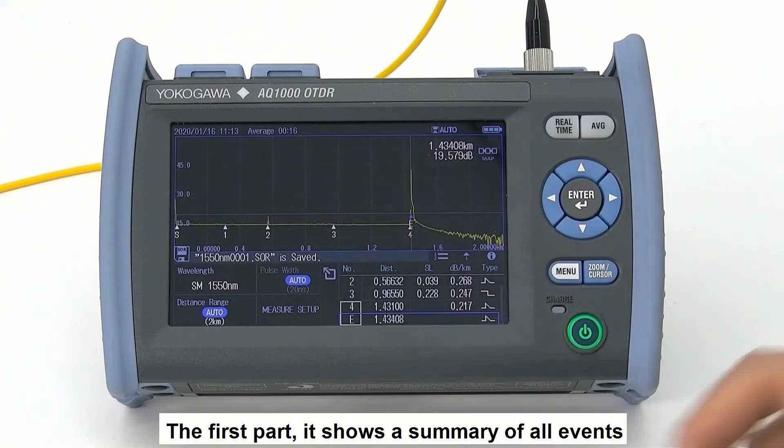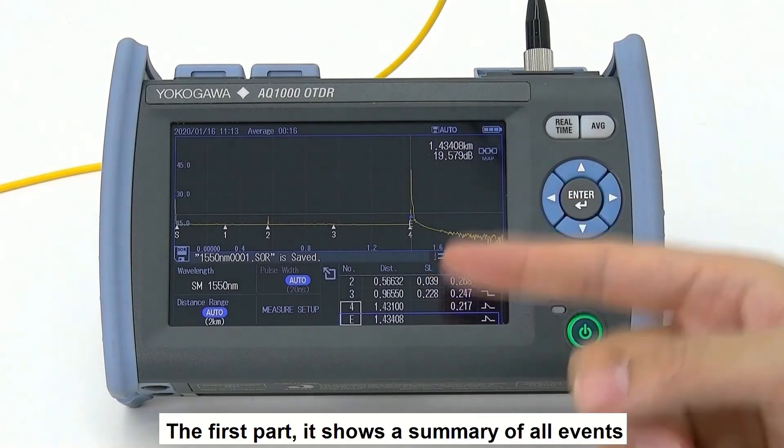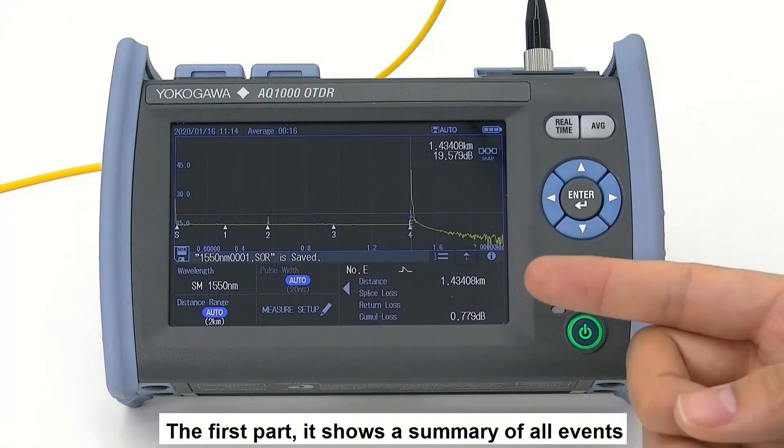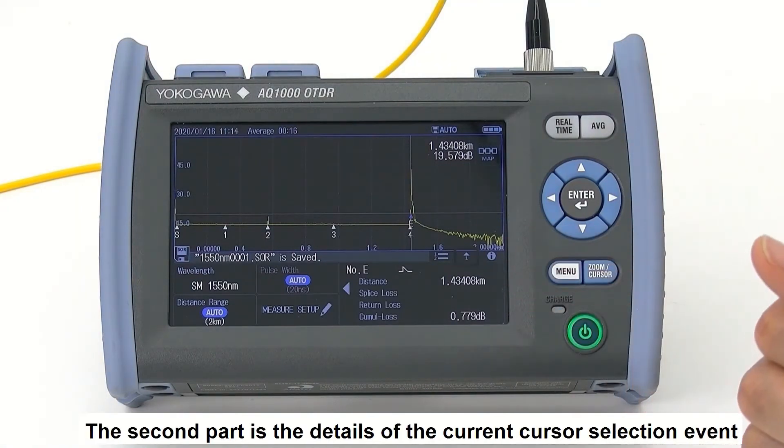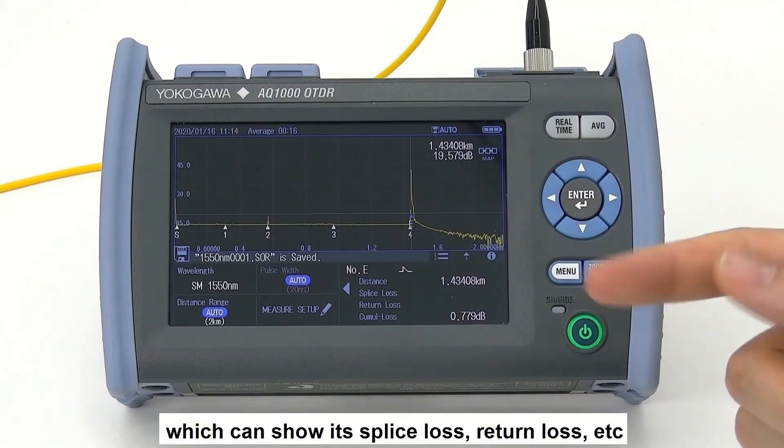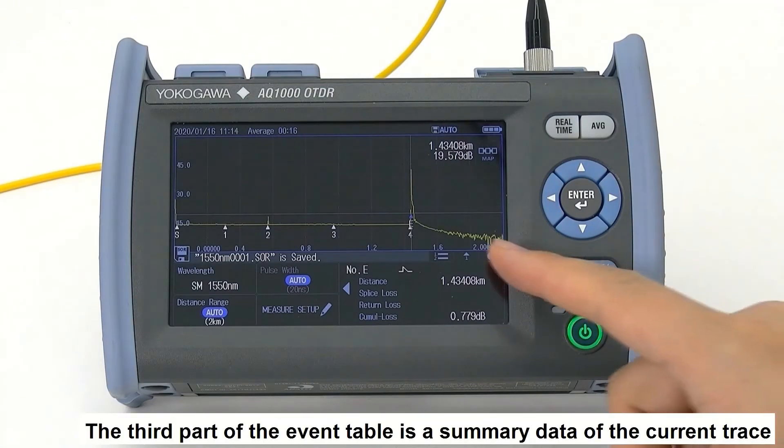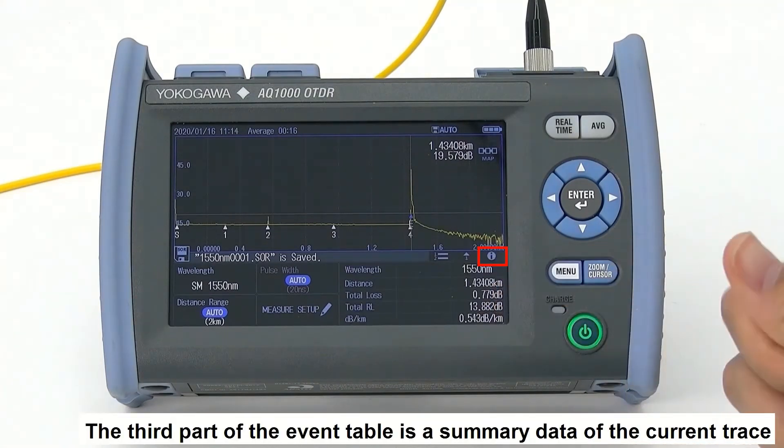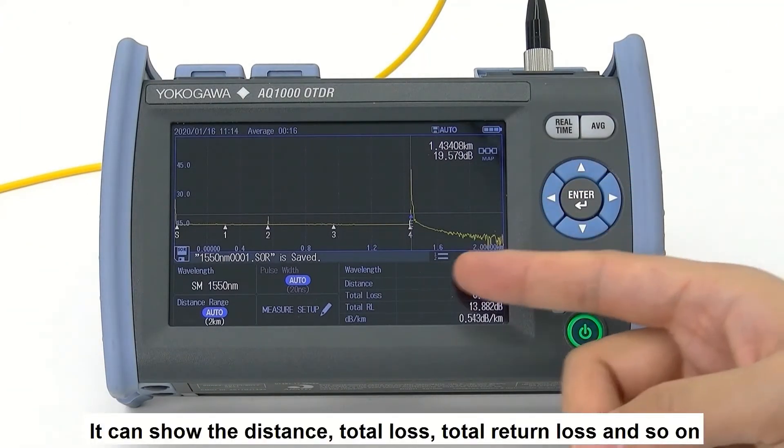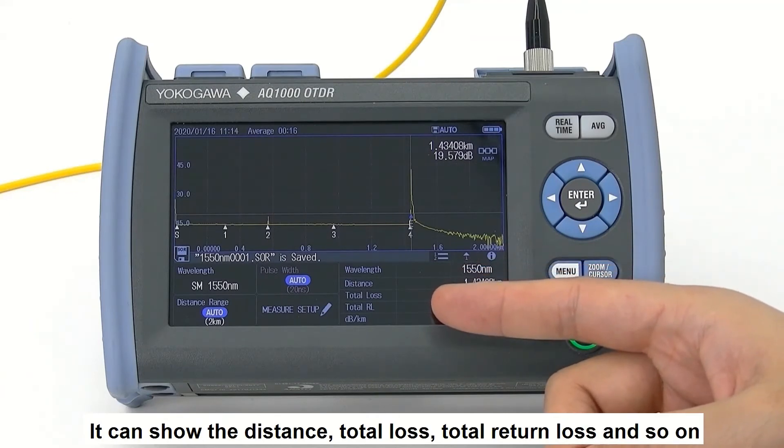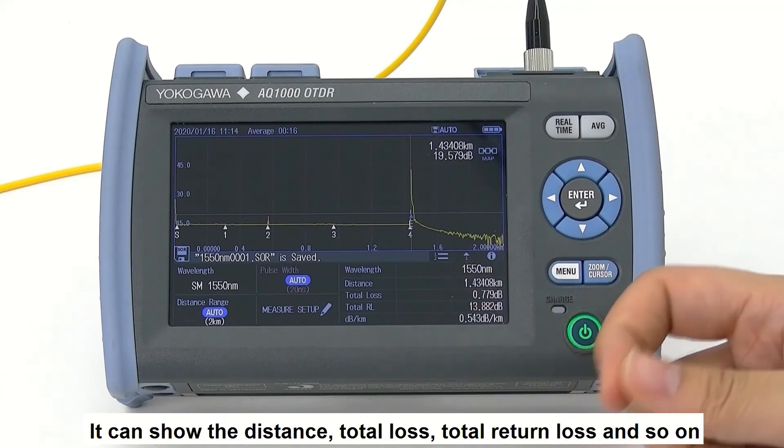The first part is a summary of all events. The second part is the detail of the current cursor selected event, which can show its splice loss, return loss, etc. The third part of the event table is the summary data of the current trace. It can show the distance, total loss, total return loss, and so on.